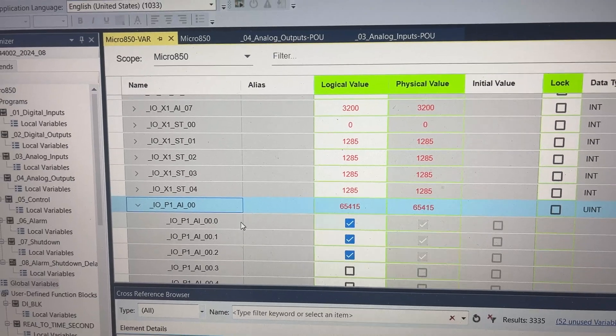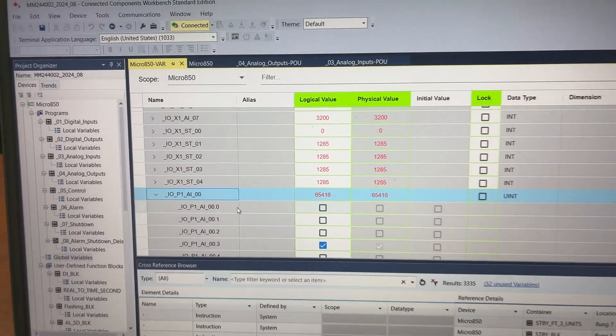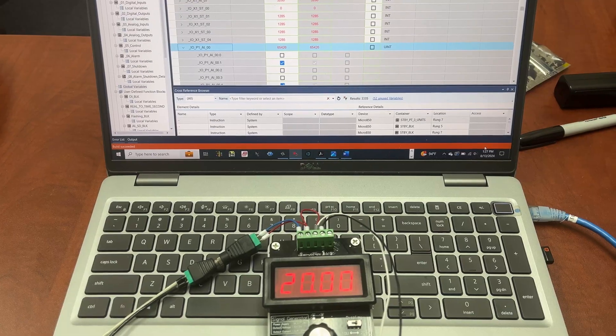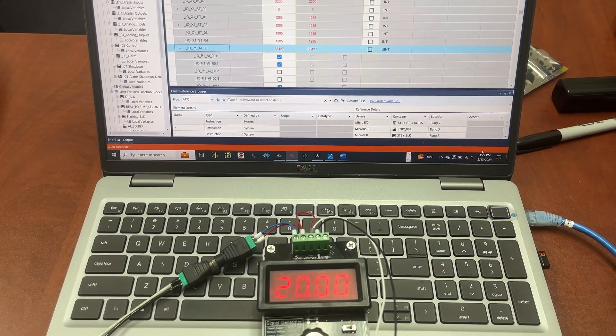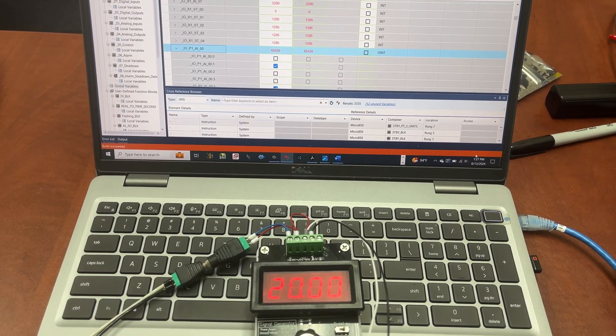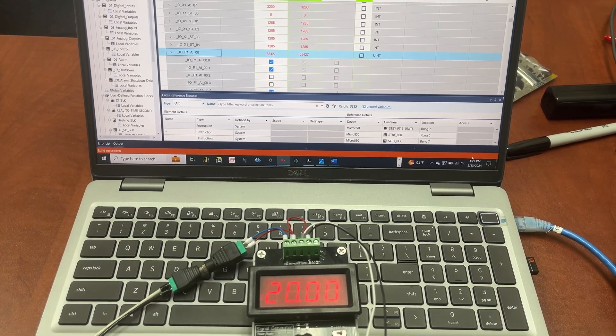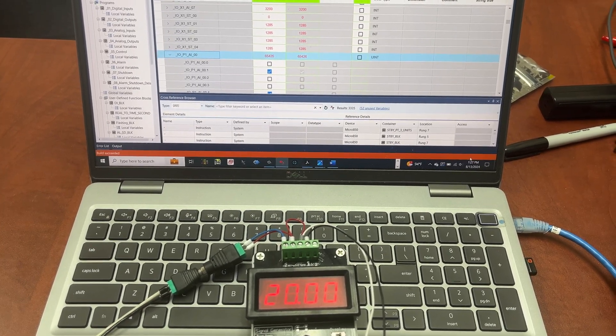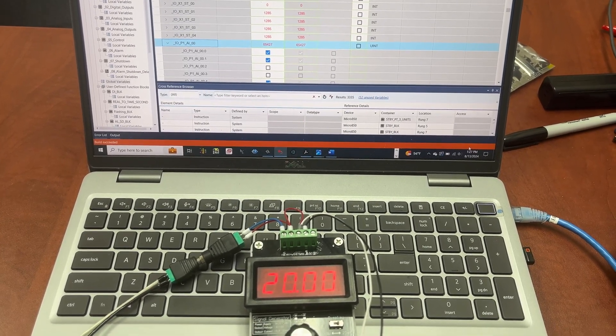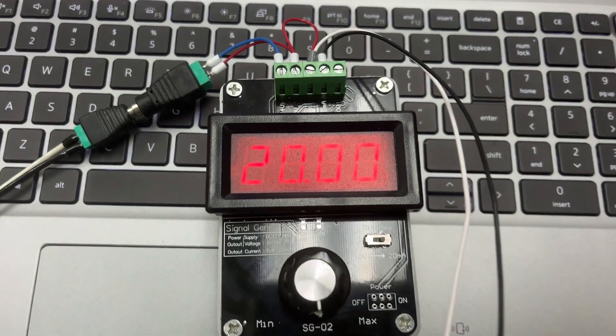It is off a bit, but it is very close to 65,520 for the 20 milliamp signal.